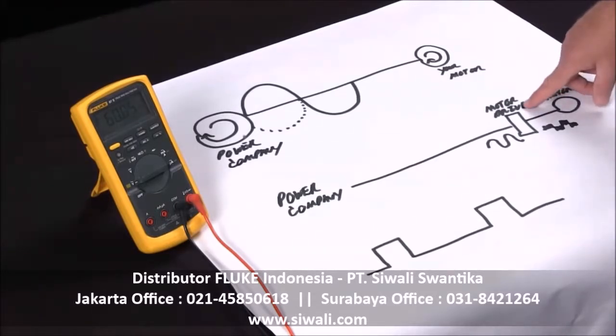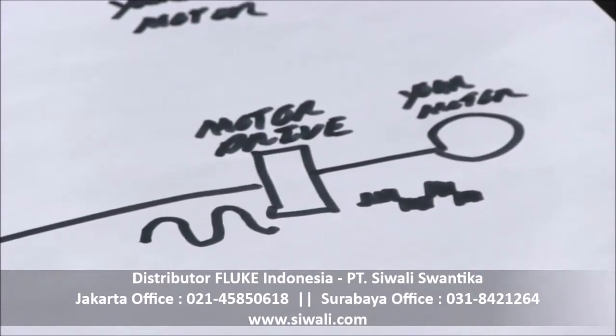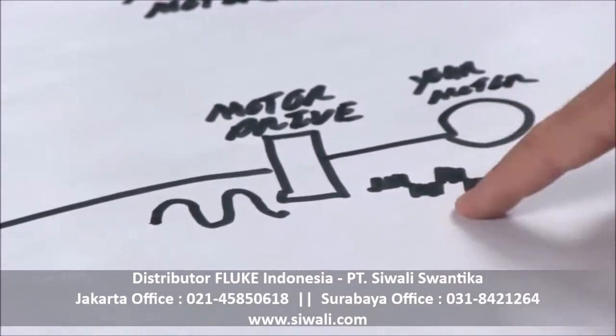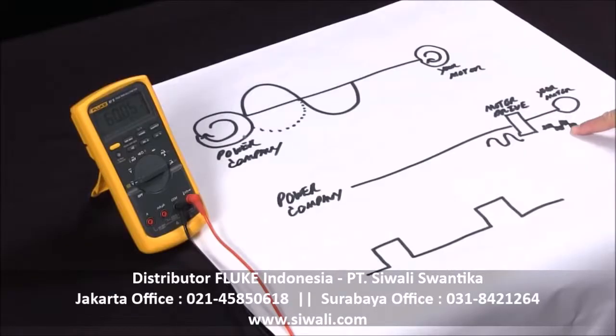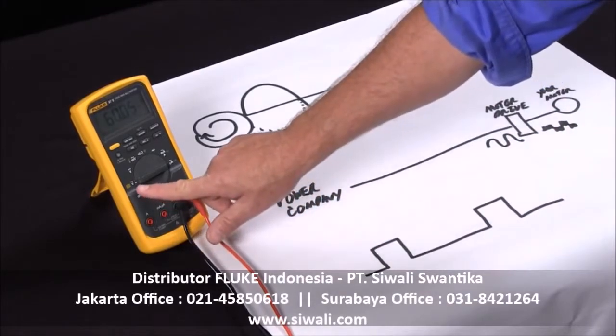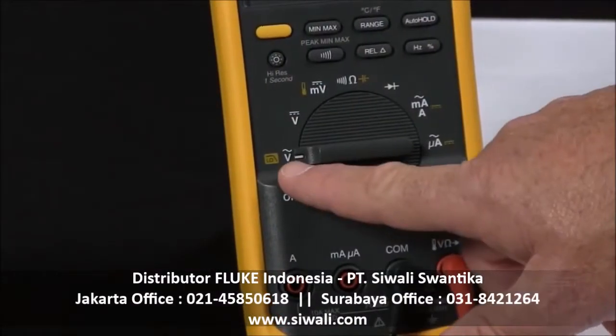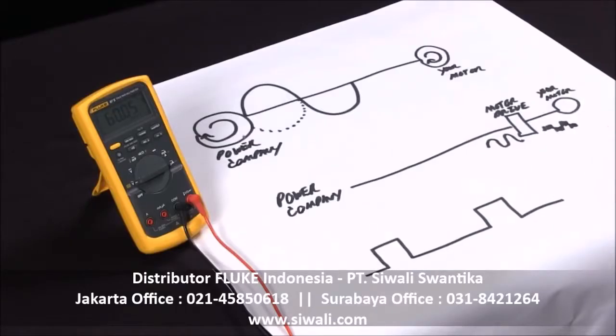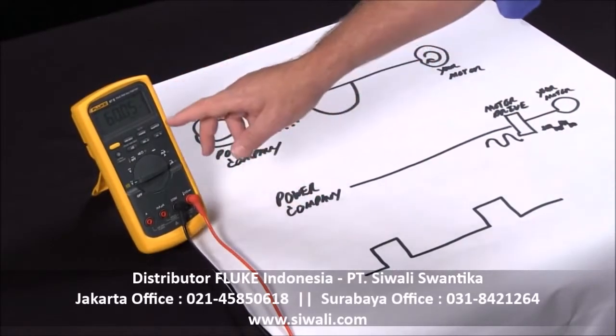As you get more into working with motor drives, this measurement becomes a little bit more complex because the motor drive takes your normal sine wave and puts it into a pulse width modulated, or PWM, signal. A normal multimeter is not going to be able to measure this frequency properly. We added a feature on the Fluke 87V and our 1587 — next to the AC volts there's a low pass. By hitting this yellow button, I've converted this into a special measurement mode that will measure this PWM signal accurately, giving you the frequency and duty cycle function.